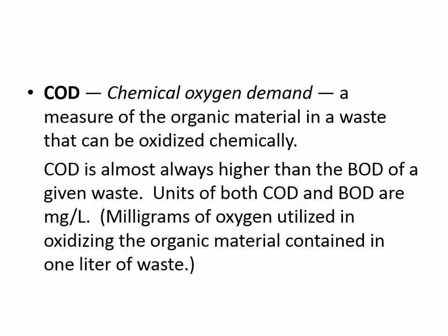Another term that we'll come across during the semester is chemical oxygen demand. So far we've been talking about biochemical oxygen demand, meaning just the bacteria are using oxygen. Well, there are also going to be some things in the wastewater that the bacteria aren't breaking down, but a reaction to dispose of that other waste would still demand oxygen. Gasoline is an example. If you have gasoline dissolved in water, bacteria aren't usually going to use it; there may be some exotic bacteria that could use a little bit of gasoline for respiration, but in general, there isn't going to be a lot of biochemical oxygen demand for gasoline mixed into water. But there would be a chemical oxygen demand if you're doing a chemical reaction to break down that gasoline in the water. It has the same units as BOD, milligrams of oxygen per liter of the waste.